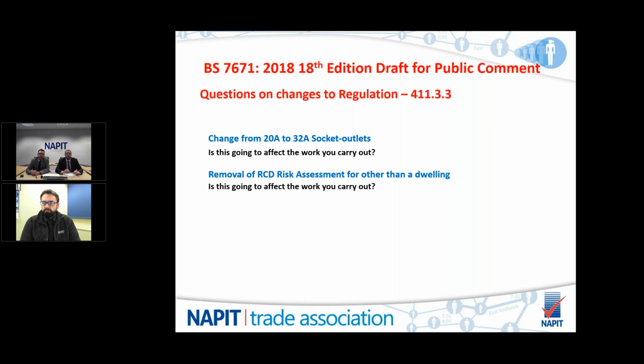The removal of the RCD risk assessment for other than the dwelling. This has been in effect, and part of the reason for removing it is that there has been a bit of abuse of the RCD risk assessment. Do you have any questions on that that's come through? Right, does this mean we will have to install RCDs for all socket outlets in offices? Again, similar to the last one, yes, this now falls under the regulation and would require RCD protection on all socket outlets. However, as we've said, if this forms a large part of your business and you feel that would be damaging to it, then it would be for you to put in a comment and a proposal to modify that, should you feel it would damage your business by just bringing that straight in. In the same way that NAPIT have taken on board the issues that the events industry would have, by putting forward a proposal in 711.